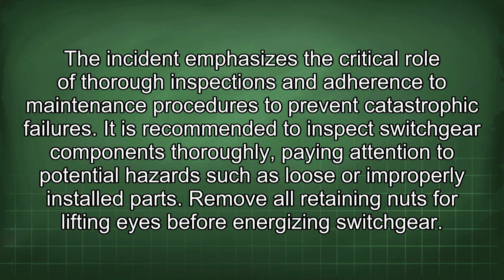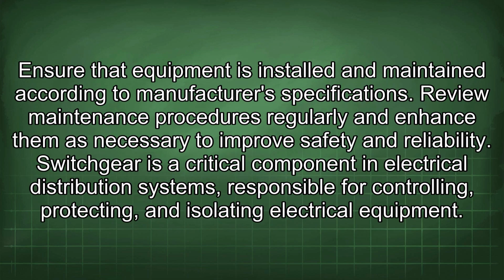It is recommended to inspect switchgear components thoroughly, paying attention to potential hazards such as loose or improperly installed parts. Remove all retaining nuts for lifting eyes before energizing switchgear. Ensure that equipment is installed and maintained according to manufacturer specifications. Review maintenance procedures regularly and enhance them as necessary to improve safety and reliability.